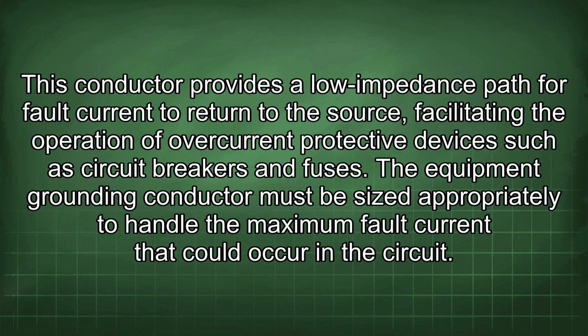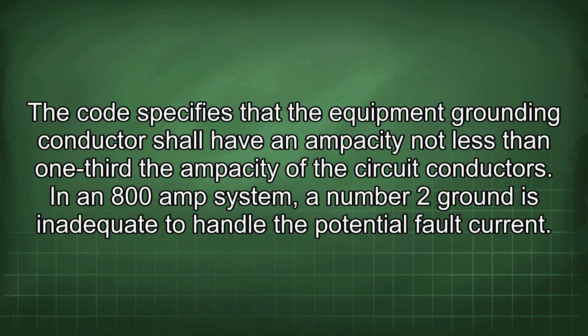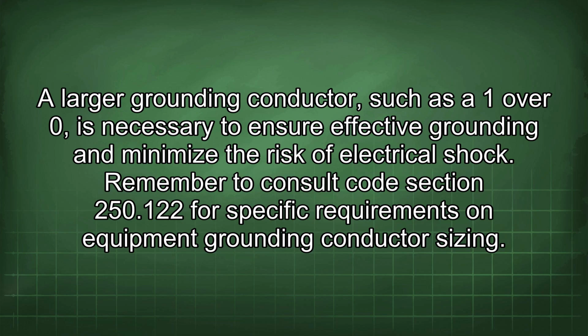Next, consider the equipment grounding conductor as specified in Code Section 250.148. This conductor provides a low impedance path for fault current to return to the source, facilitating the operation of overcurrent protective devices such as circuit breakers and fuses. The equipment grounding conductor must be sized appropriately to handle the maximum fault current that could occur in the circuit. The code specifies that the equipment grounding conductor shall have an ampacity not less than 1/3 the ampacity of the circuit conductors. In an 800 amp system, a number 2 ground is inadequate to handle the potential fault current. A larger grounding conductor, such as a 1/0, is necessary to ensure effective grounding and minimize the risk of electrical shock. Remember to consult Code Section 250.122 for specific requirements on equipment grounding conductor sizing.